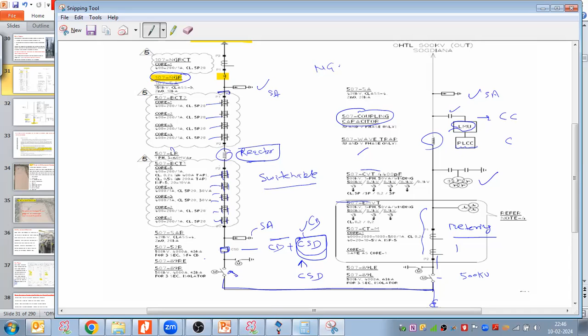So after the reactor, again we have connected the surge arrester. And after that, if you see, I have used NGR here. Do not confuse NGR with neutral grounding resistor, because there is one more NGR in the electrical system, which is the neutral grounding resistor. But in case of a substation, when this reactor is connected, the NGR connected with the reactor is not the neutral grounding resistor. It is called the neutral grounding reactor, NGR, which I'm connecting in series with the reactor, and then it is going to the earth. So this is how we represent the concept through the single line diagram.